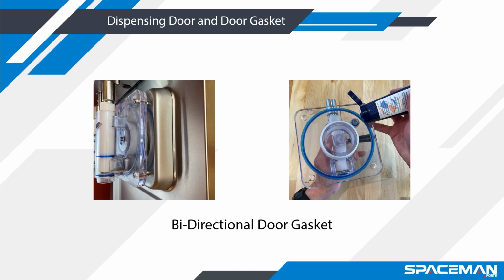Newer door gaskets with ridges on the outside do not need to be lubricated, as they seal better than the older flat gaskets. All newer tune-up kits should have these newer door gaskets, and they are backwards compatible from version 3 all the way back through version 1.